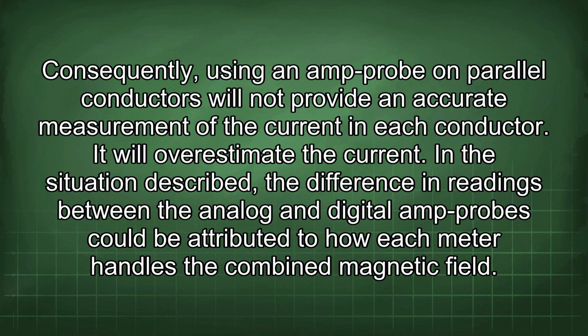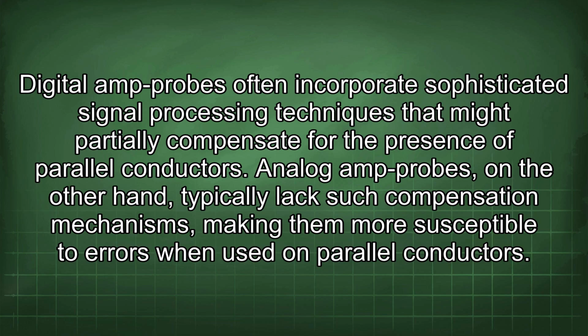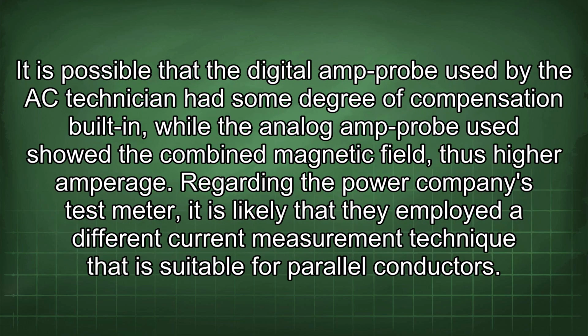In the situation described, the difference in readings between the analog and digital amp probes could be attributed to how each meter handles the combined magnetic field. Digital amp probes often incorporate sophisticated signal processing techniques that might partially compensate for the presence of parallel conductors. Analog amp probes, on the other hand, typically lack such compensation mechanisms, making them more susceptible to errors when used on parallel conductors. It is possible that the digital amp probe used by the AC technician had some degree of compensation built in, while the analog amp probe showed the combined magnetic field, thus higher amperage.